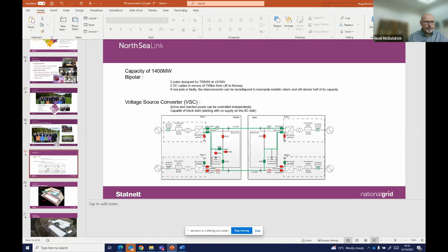As Caroline indicated, we built a voltage source converter station, and we've gone for a bipole arrangement with two poles, each capable of providing 700 megawatts of transfer capacity. We operate in what we call a rigid bipole, so each pole is loaded to the same level as the other. One pole operates at plus 515 kV and the other at minus 515 kV, giving a total of 1 million volts across the two poles. We can transfer 1,400 megawatts in either direction, which with 1 million volts gives an operating current of about 1,400 amps.